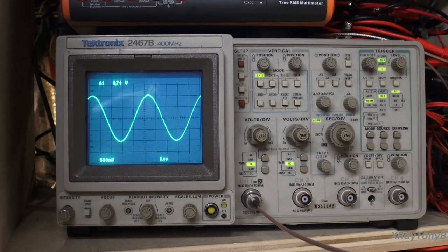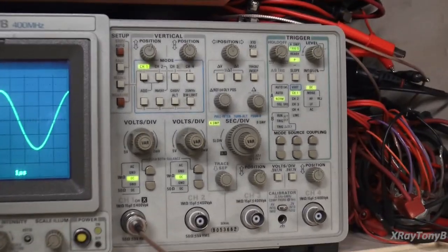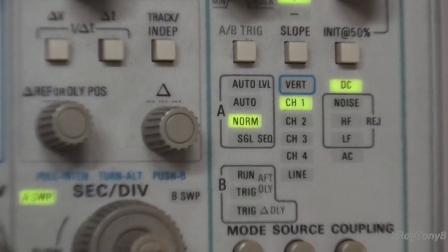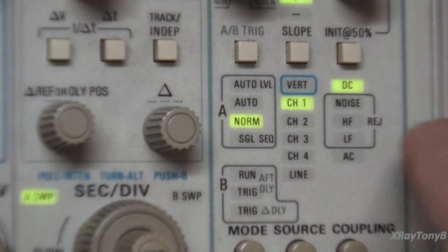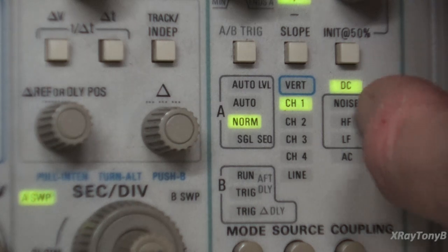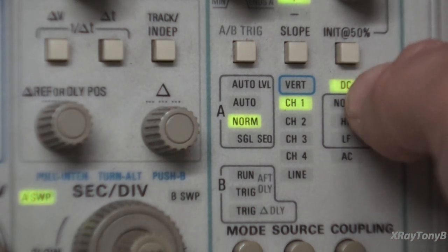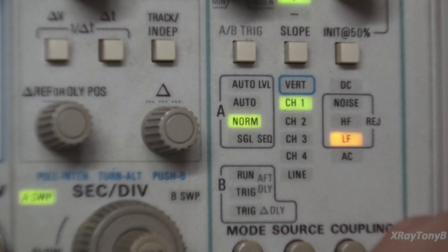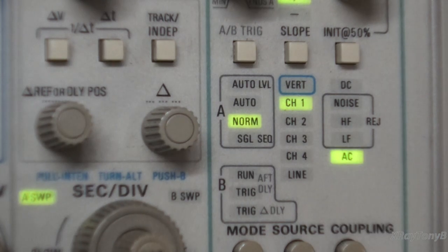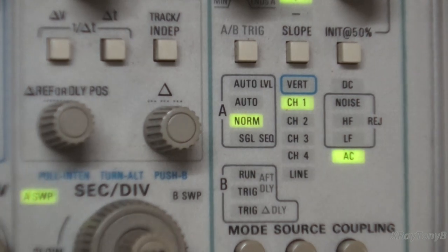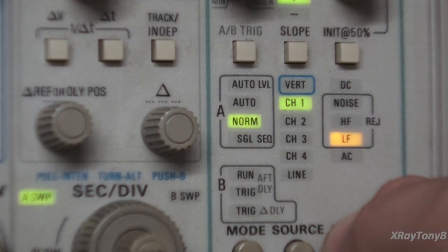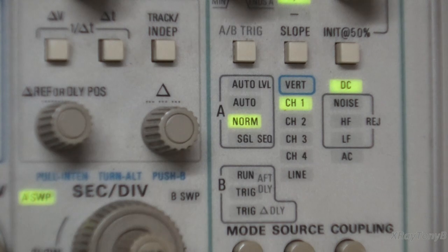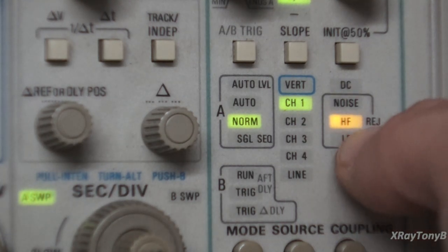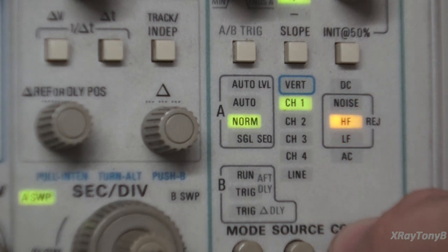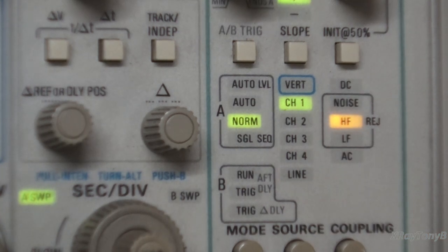Now, some of the more expensive oscilloscopes, and you will not see this on some of the lower end, cheaper 20 megahertz scopes, can actually have different couplings on your trigger as well. They all have DC coupling and AC coupling, just like your volts per division. But more than that, we can actually reject certain things. You'll see noise reject, high frequency reject, and low frequency reject. I have it set to high frequency reject right now.